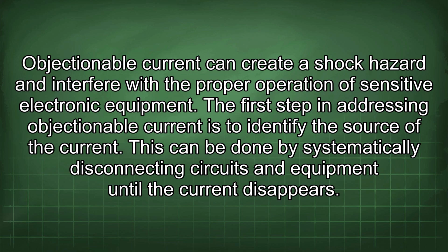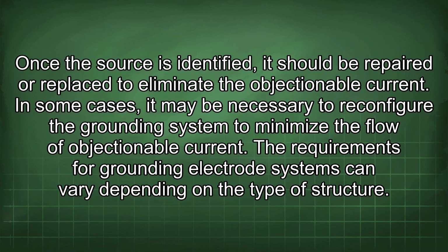The first step in addressing objectionable current is to identify the source of the current. This can be done by systematically disconnecting circuits and equipment until the current disappears. Once the source is identified, it should be repaired or replaced to eliminate the objectionable current. In some cases, it may be necessary to reconfigure the grounding system to minimize the flow of objectionable current.